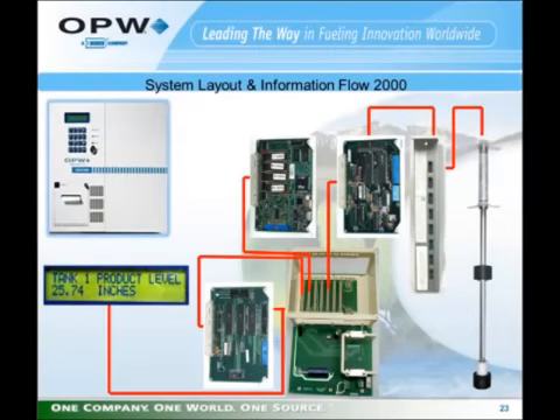For the EECO 2000, it's a bit more complicated because the EECO 2000 architecture is built on a card cage concept, where there are separate circuit boards in the card cage performing specific functions that are all done on the same board in the EECO 1500. So in the illustration that we're looking at here, the tank probe connects to a tank level monitor probe interface module, which then feeds into a tank level monitor driver board, which through the backplane board is connected to the MPU or processor board, which then feeds data to the auxiliary board, and the auxiliary board then feeds data to the display and to the printer.